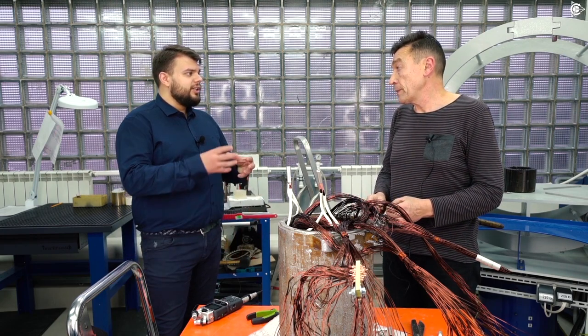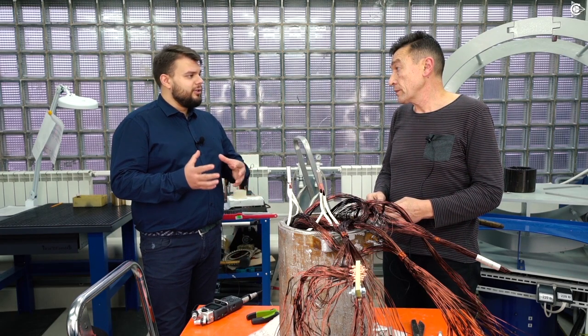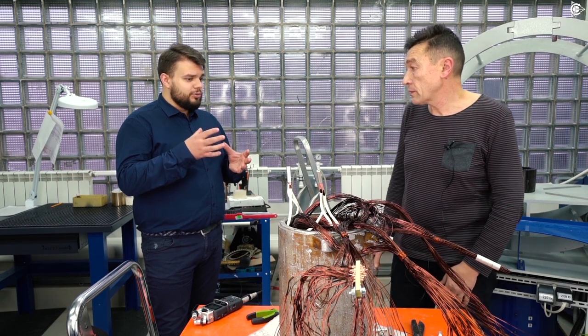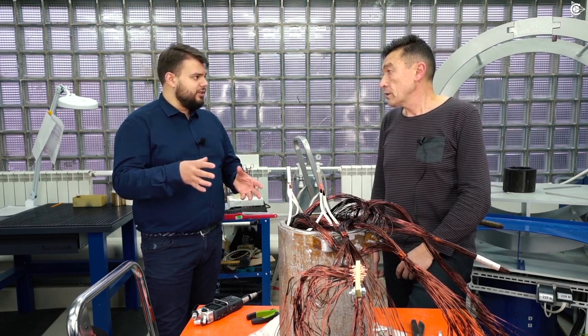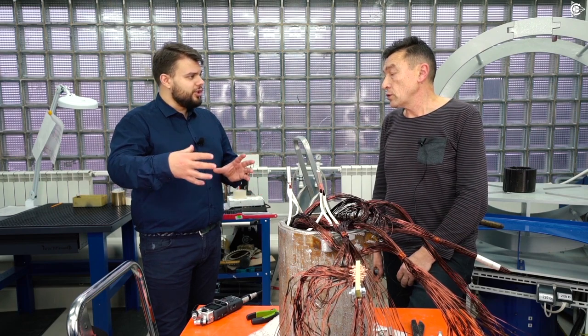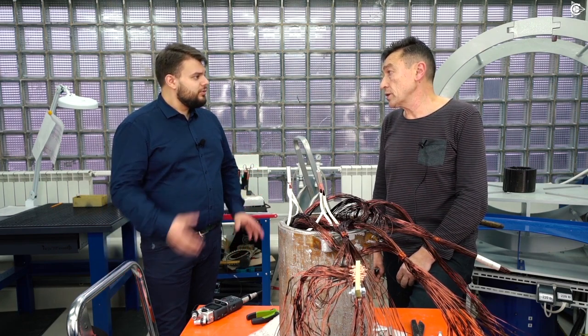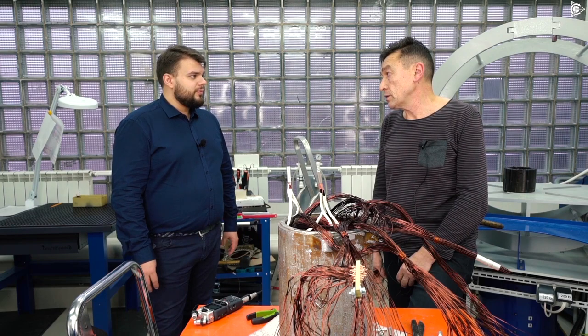In the same physical size, the 7.5 kilowatt motor will operate just as well, but it will demonstrate the performance and currents of a 9 kilowatt motor. Roughly speaking, if we take not Slavyanka but a classic motor, we would need to install a 9.5, 10, or even 11 kilowatt motor instead.